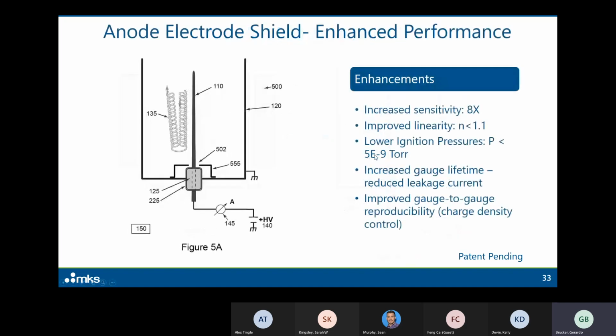When we did this, we found that not only did we solve the problem we were seeing with the feed-throughs, but we actually overshot. We had even better sensitivity than in the original prototypes, about 8 times more, which was great. We improved the linearity; we don't ship product that has a linearity higher than 1.1. We lowered the ignition pressures.